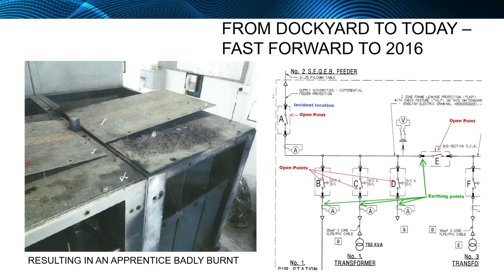Now the panel that was removed, I'm not really sure whether it had a tick or cross because it was blackened, but on the right hand side you can see the circuit diagram, and the incomer side was where the accident happened. It hadn't been isolated from that side. So this person was terribly burnt, and they'd actually opened the panel that was on the livened side. Not a good outcome.